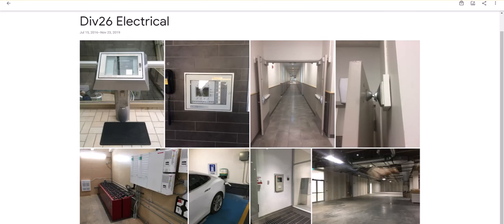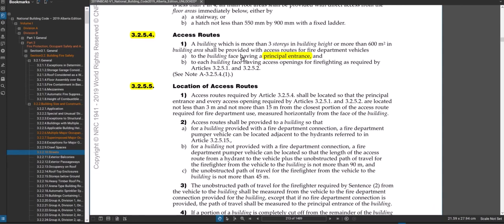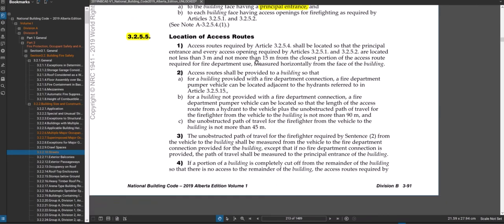That's why they want to go to the principal entry first in larger buildings — so they're not running around looking. Here's an example of a freestanding annunciator in a glass vestibule with no wall, so it's on its own pedestal. The next part covers location of access routes, which essentially tells you the truck has to be able to get close to the principal entry — between three and 15 meters from it. Even if you have an internal roadway, the entry can't be too far from that roadway.